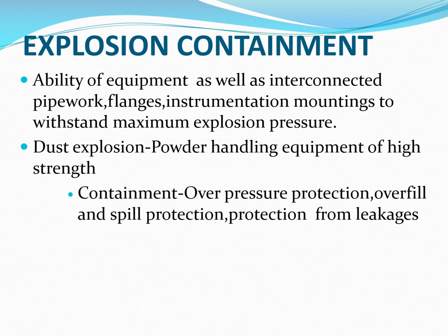Explosion containment refers to the ability of equipment, as well as all interconnected pipework, flanges, instrumentation, and mountings, to withstand the maximum explosion pressure. Containment of explosion pressures developed by dust explosions requires powder handling equipment of high strength — specifically, equipment capable of withstanding pressures in the range of 7 to 10 bar gauge. Containment includes overpressure protection, overfill and spill protection, and protection from leakages.